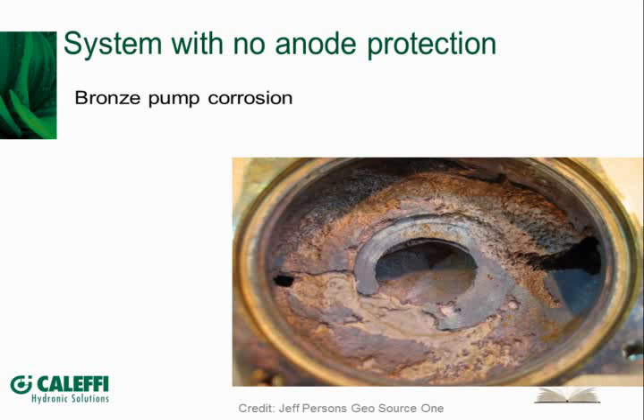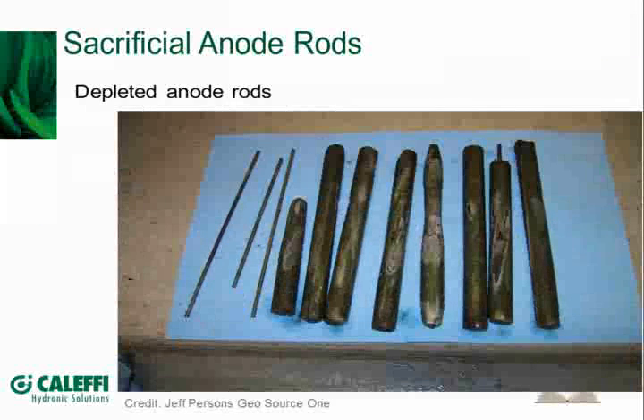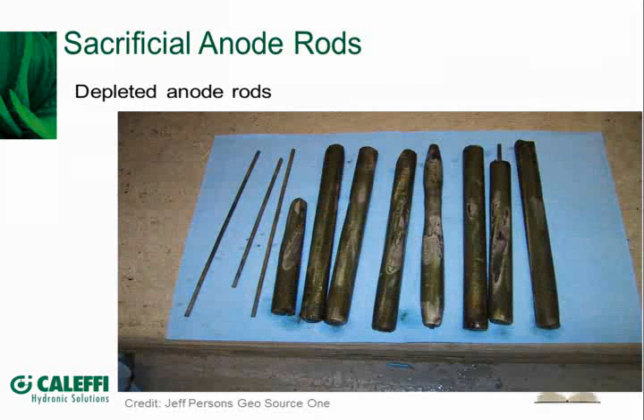Well, the next, shall we say, least noble material in the system to those stainless water tanks was the bronze pump and the copper piping in the home. And the customer was complaining about green stains in their sinks and tubs and so forth. I really didn't take too much stock in it until I got a call that said, we've got water on the basement floor and it's coming out of this geothermal machine, and we found this circulating pump essentially totally eaten up on the inside of the pump body.